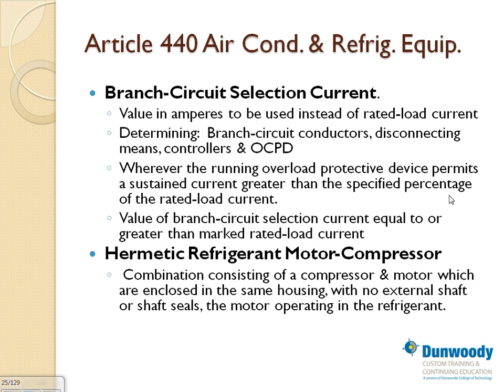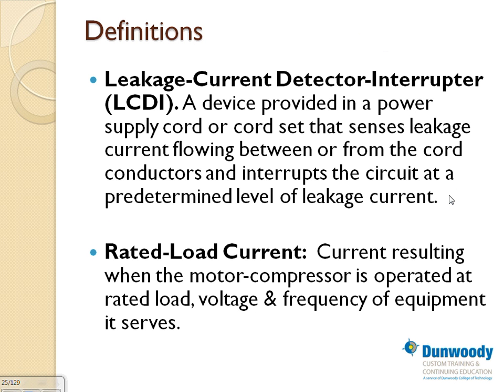And again, the reason they have two currents on this equipment is the way they act when they work together. That's a special type of motor. They call them hermetic refrigerant motor compressors. They're enclosed in the same housing with no external shaft or shaft seal, the motor operating in the refrigerant. So they're acting as a unit, unlike a fan on a roof, which acts by itself and is not tied to any refrigerant cycle or anything else. Because it's a combo, they act like a standalone unit. So they're different than just a motor by itself. They act differently than a motor.